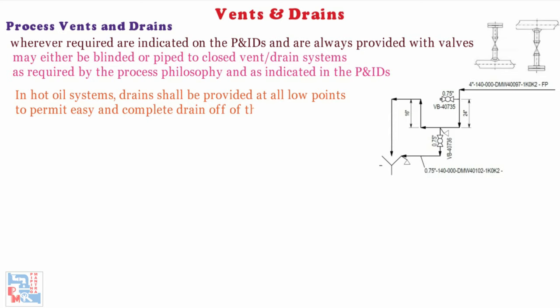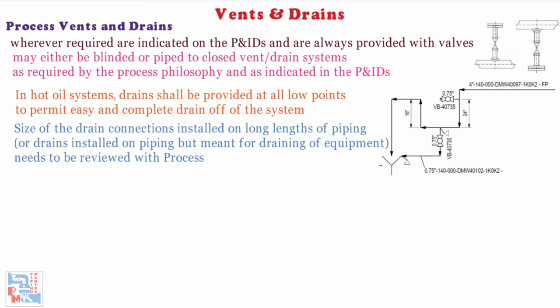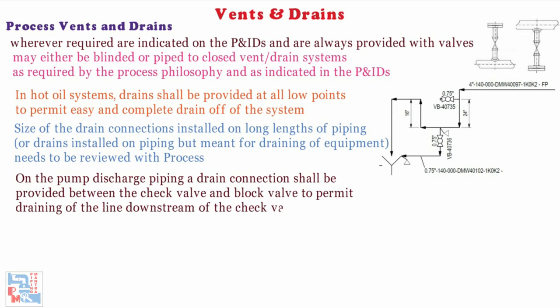The drains should be connected to the hot oil drain system. The size of drain connections installed on long lengths of piping, or drains installed on piping but meant for draining of equipment, needs to be reviewed with the process team for the emptying time. On the pump discharge piping, a drain connection shall be provided between the check valve and block valve to permit draining of the line downstream of the check valve. This drain connection shall be indicated in the P&ID.